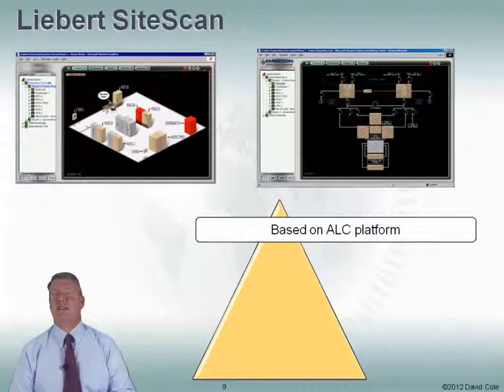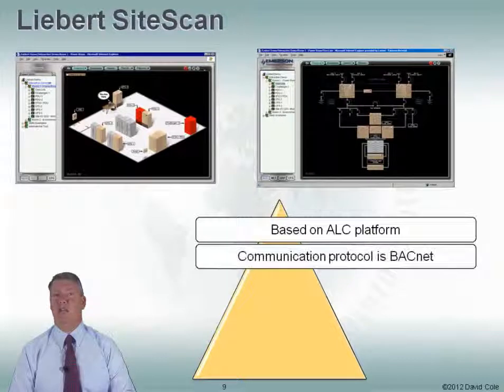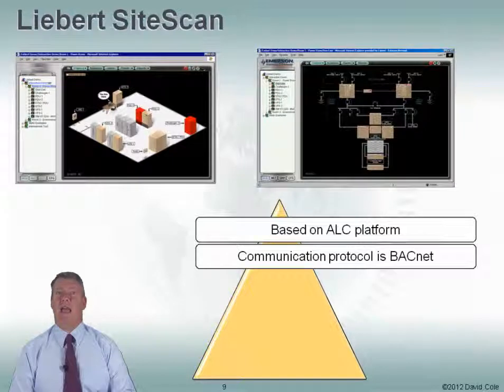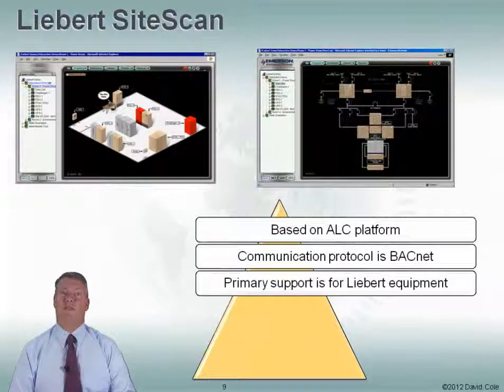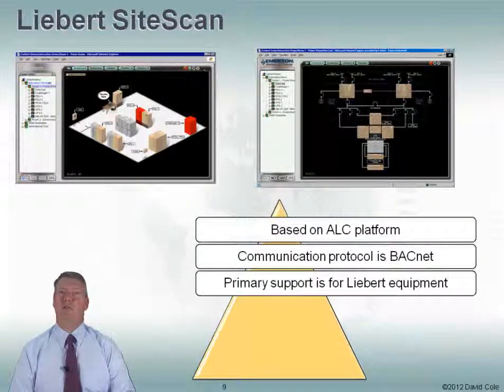Liebert SiteScan is actually based on an automated logic controls platform — Liebert doesn't own the platform, but they've made extensive customizations to it, making a really nice package. It's very widely used in the industry. The base communication protocol is BACnet, although they have some protocol converters that allow them to work with other devices. Primary support is for Liebert equipment, and you'll see that with a lot of hardware manufacturers — they'll support their own equipment very well and then have add-ons to support equipment from other manufacturers.